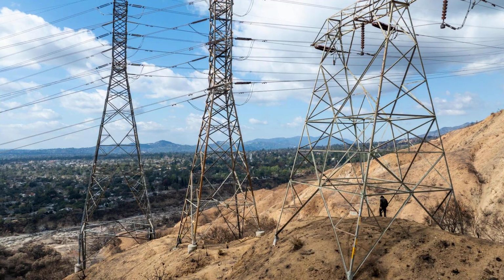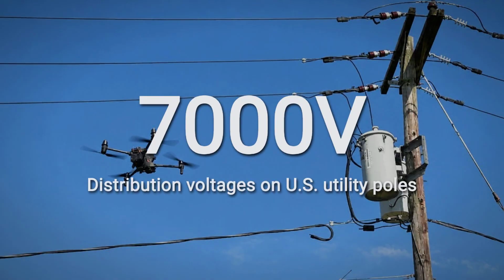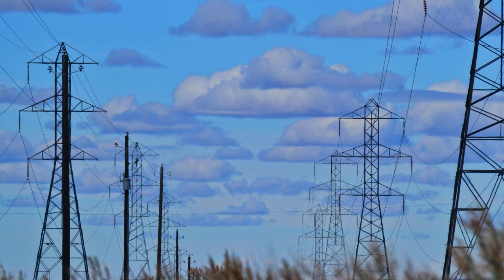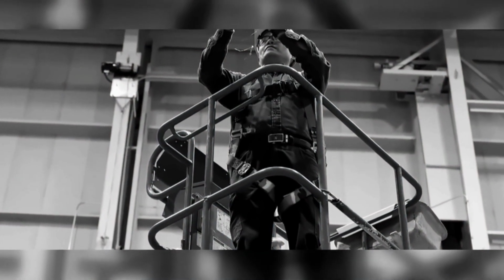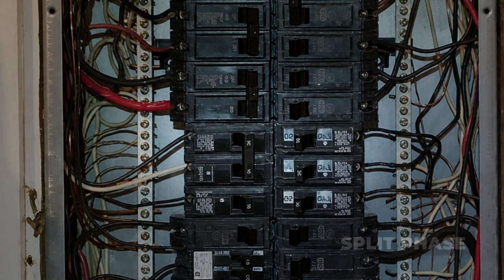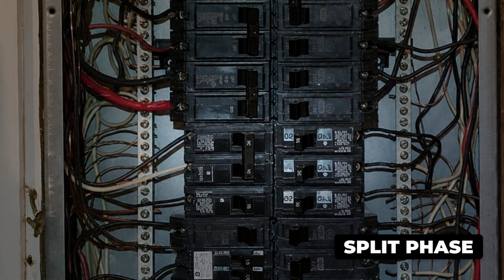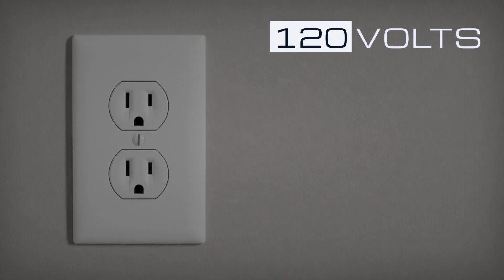The path of electricity from power plants to neighborhoods requires a practical balancing act between physics and safety. To transmit power over long distances without massive losses, utilities must push it through distribution lines at high voltages, often exceeding 7,000 volts. This method ensures efficient travel across the electrical grid, but the raw force is completely incompatible with everyday household systems. In the United States, standard home appliances, lights, and wall outlets are designed to use a split-phase service of 120 volts and 240 volts.